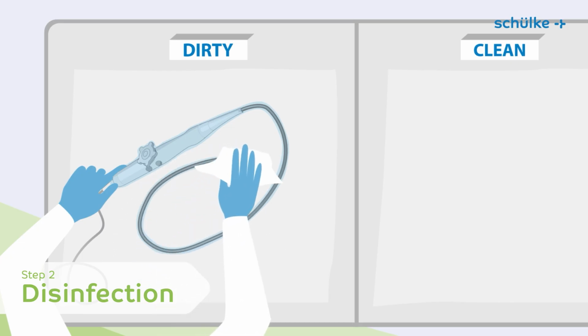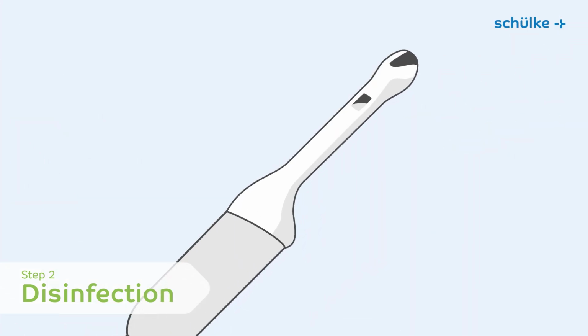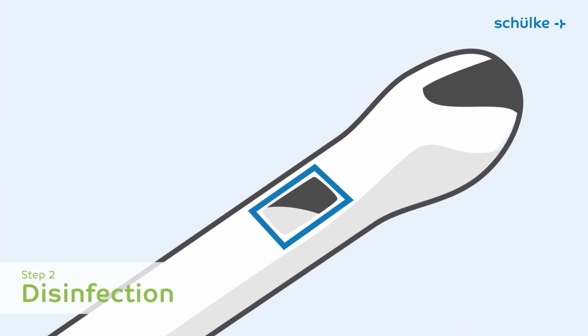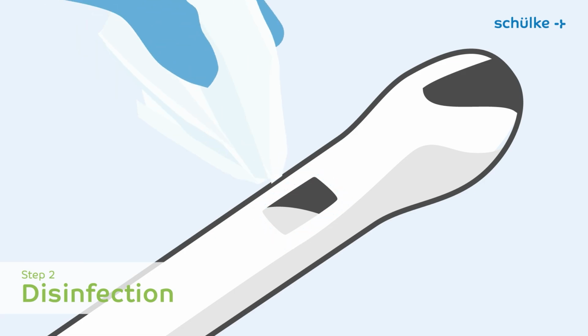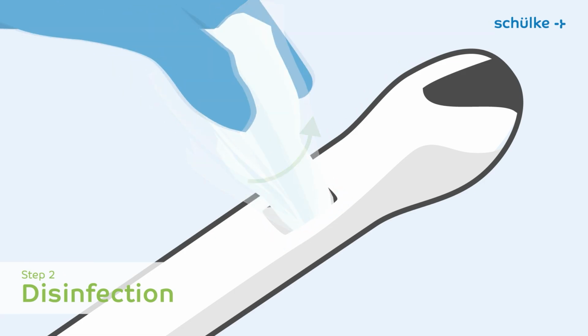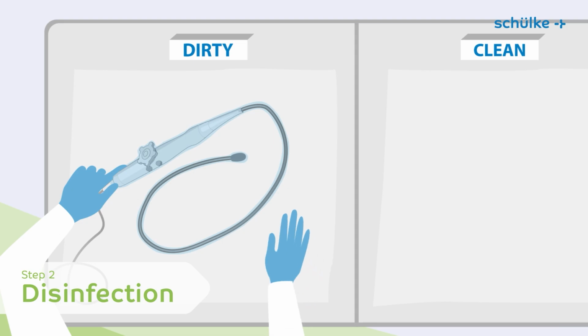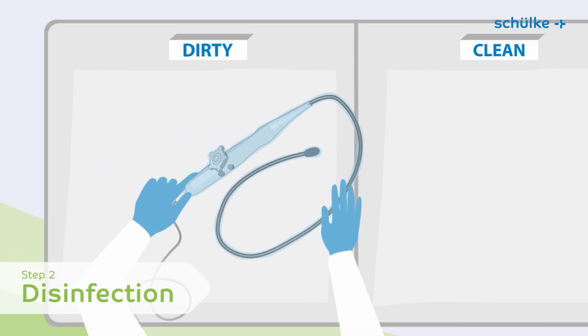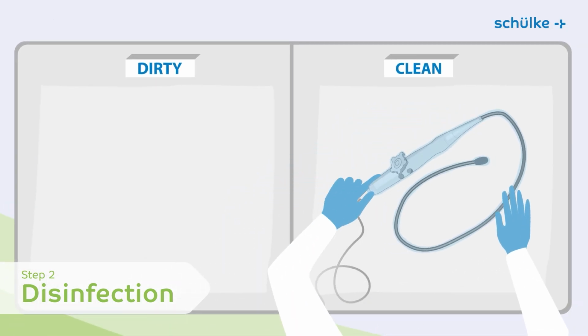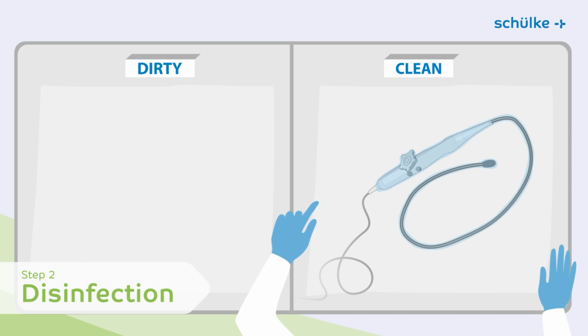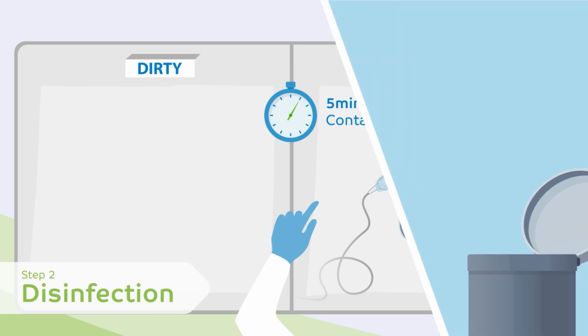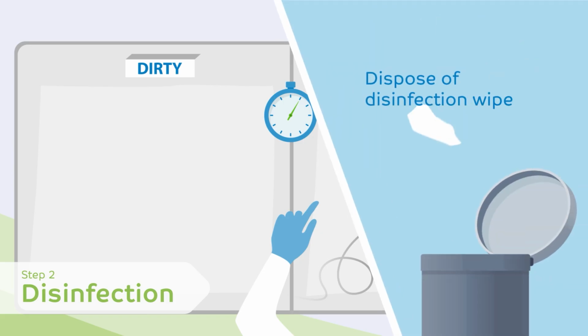Pay particular attention to joints, edges, and recesses of the medical device. Disinfect hard-to-reach recesses additionally by pressing in a wipe tip in a rotating motion. Ensure that the medical device is protected from recontamination during contact time, for example, by placing it in a disinfected holder or using a sterile pad. Maintain a contact time of 5 minutes. Dispose of the used disinfection wipe in accordance with local regulations.